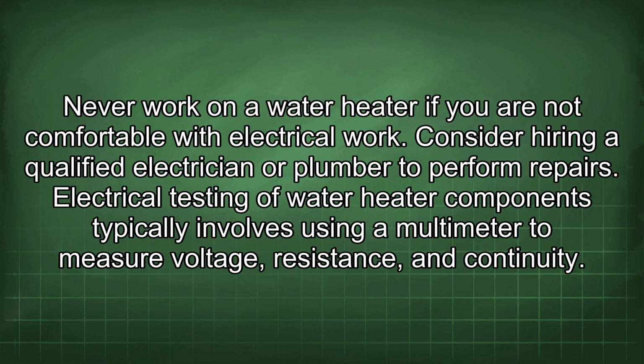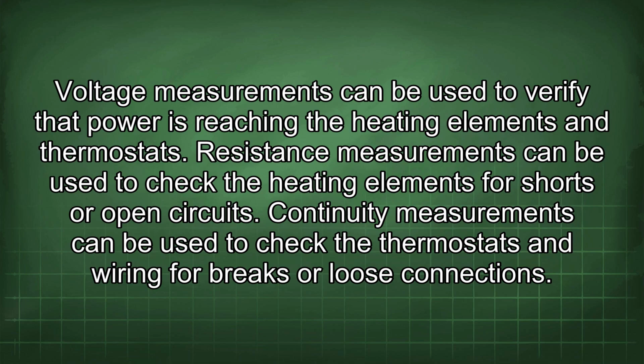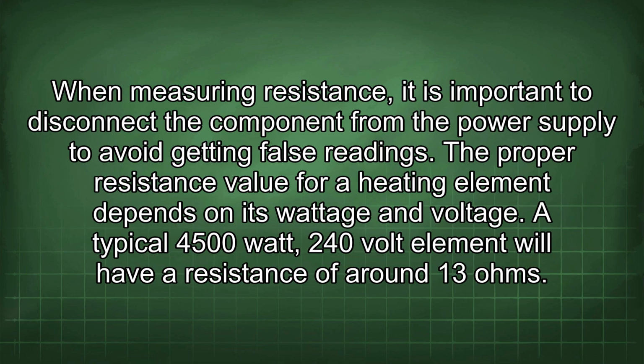Electrical testing of water heater components typically involves using a multimeter to measure voltage, resistance, and continuity. Voltage measurements can be used to verify that power is reaching the heating elements and thermostats. Resistance measurements can be used to check the heating elements for shorts or open circuits. Continuity measurements can be used to check the thermostats and wiring for breaks or loose connections. When measuring resistance, it is important to disconnect the component from the power supply to avoid getting false readings.